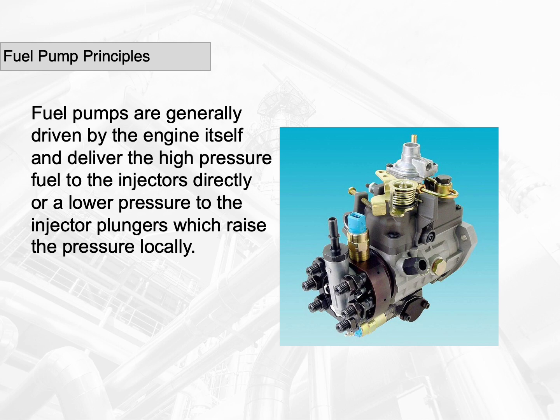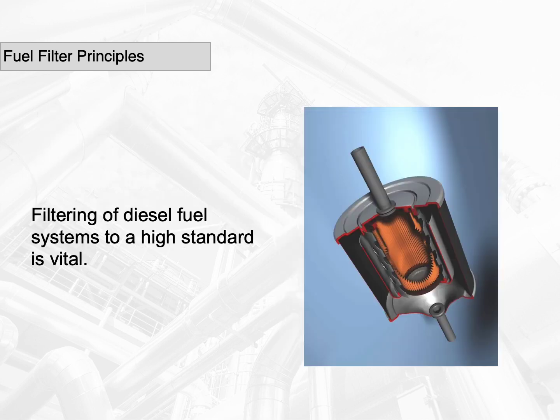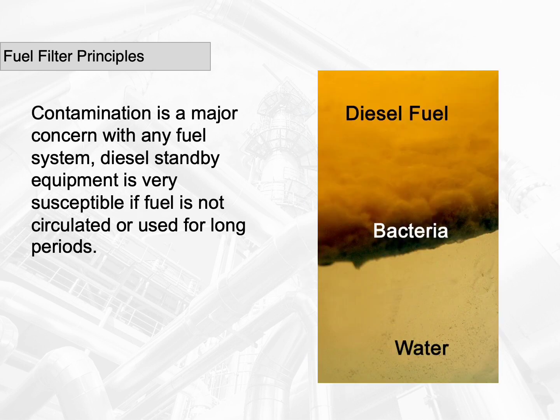Fuel pumps are generally driven by the engine itself and deliver the high pressure fuel to the injectors directly, or a lower pressure to the injector plungers, which raise the pressure locally. Fuel filter principles. Filtering of diesel fuel systems to a high standard is vital. The very high pressures and precise injection equipment will be damaged or become blocked if any sediment is allowed into the system. Contamination is a major concern with any fuel system. Diesel standby equipment is very susceptible if fuel is not circulated or used for long periods.